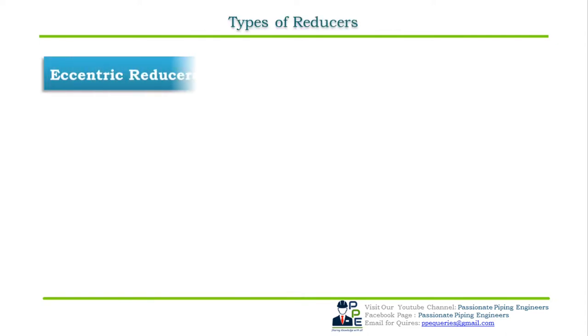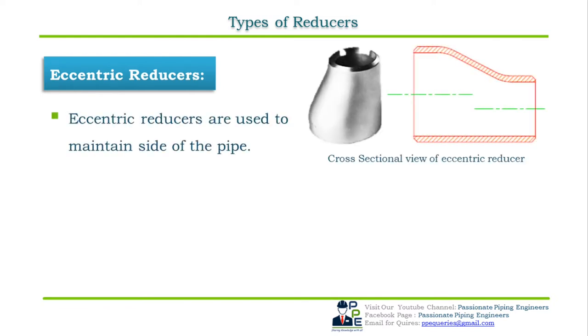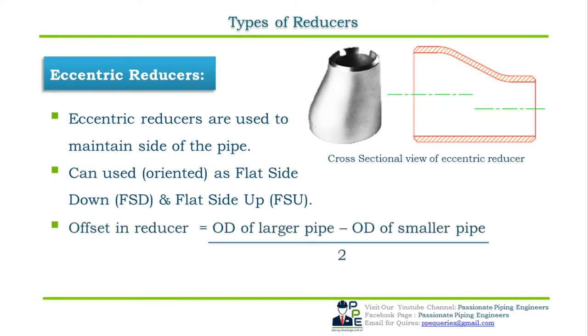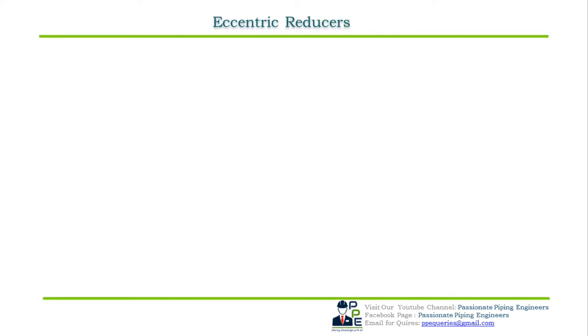Eccentric reducers are used to maintain the side of the pipe. As seen in the cross-sectional view, there are two centerlines — one for the larger diameter and one for the smaller diameter. Eccentric reducers can be oriented as flat side down (FSD) or flat side up (FSU). The offset can be calculated as: offset = (OD of larger diameter pipe − OD of smaller diameter pipe) ÷ 2. The dimensional standard is ASME B16.9.